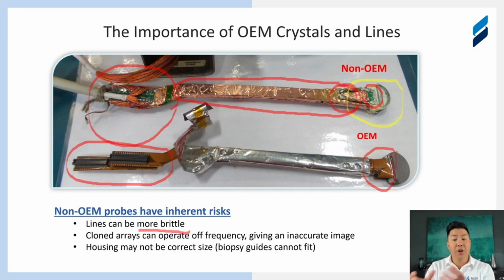because some repair companies will take non-OEM parts and put them into your probe because your OEM internals have failed, and it's masked as an OEM probe. And so now you get stuck in this vicious cycle of, why does the probe keep failing over and over again? Well, that's a leading indicator. If there's non-OEM material in there, it just isn't built to last, to be quite frank, in our opinion.